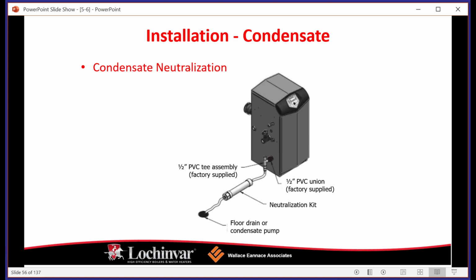So what we need to do is we need to get to a floor drain or a condensate pump, but in between those two, we need to put a neutralization kit. The reason that we use this is because the condensate that's created by combustion, due to the properties of the natural gas or the LP that we're burning, is acidic, okay?